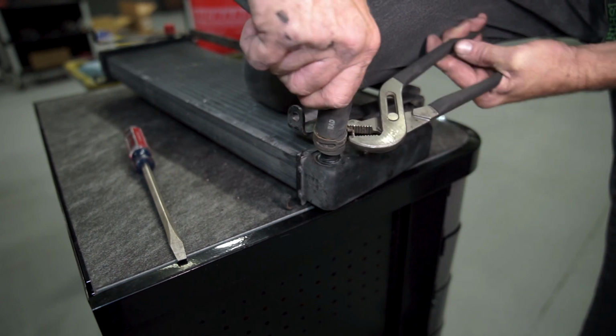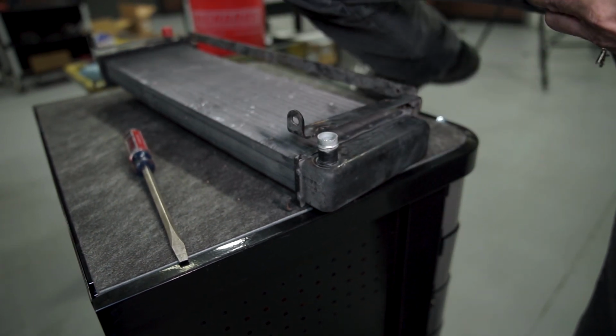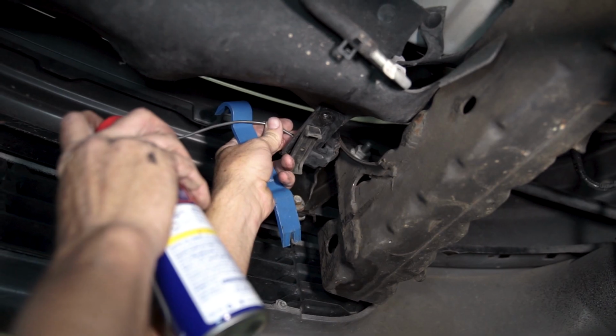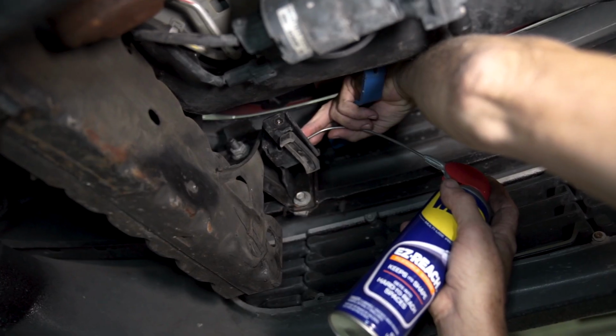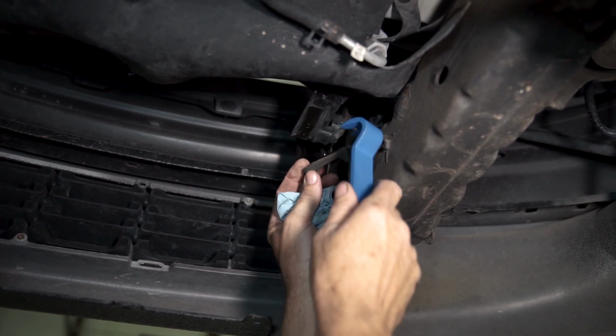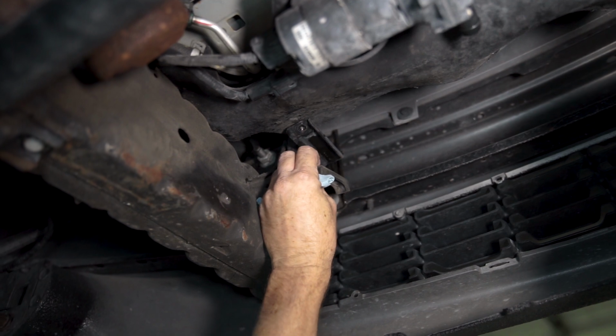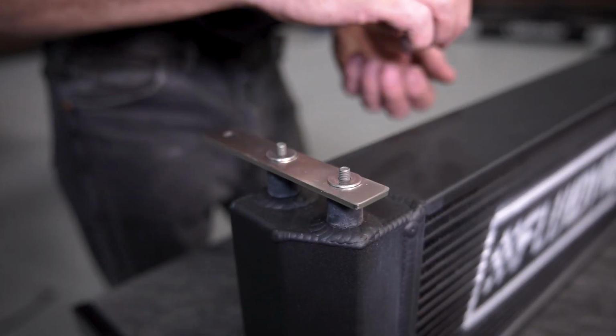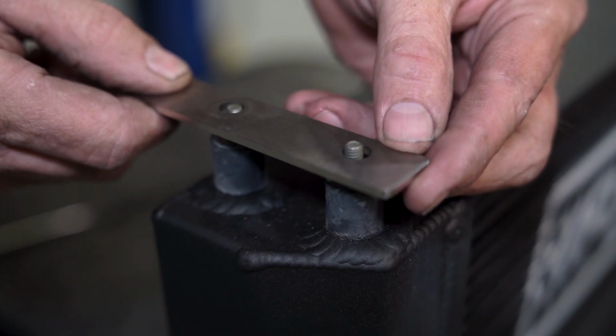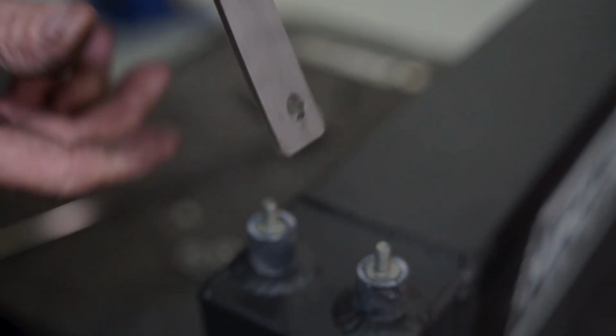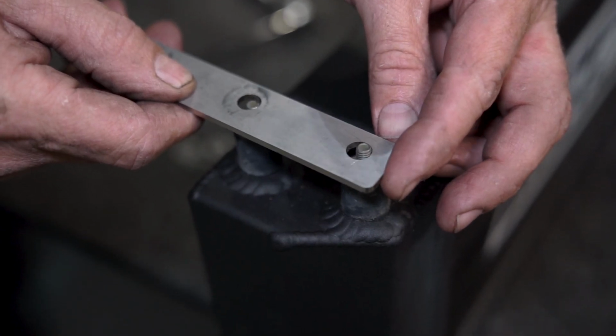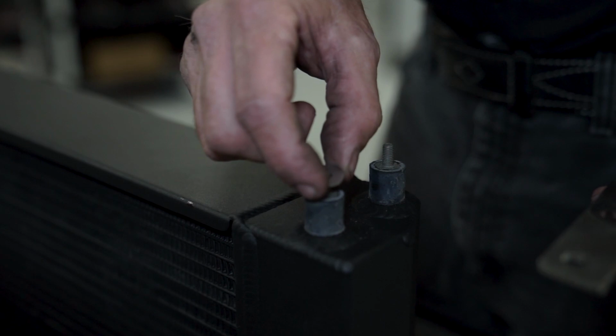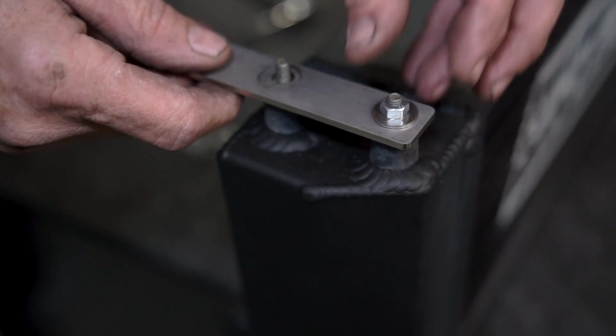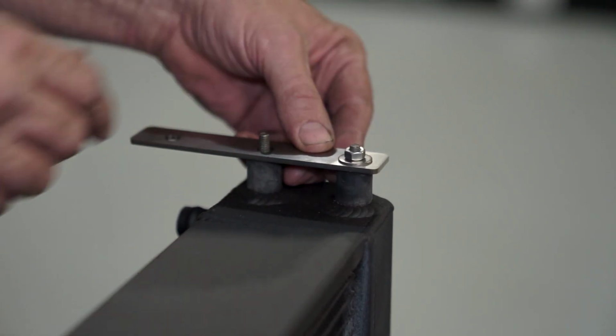Remove the hose from the heat exchanger if you had to remove the hose from the pump. Spray WD-40 on the top of each insulator. Remove them from the upper bracket. With the new heat exchanger on a workbench, remove the pre-installed brackets. Be sure and make note of how they are installed over the studs in the rubber grommet. Remove the lower washers and then reinstall each bracket. Reinstall the frontward hardware and loosely tighten.